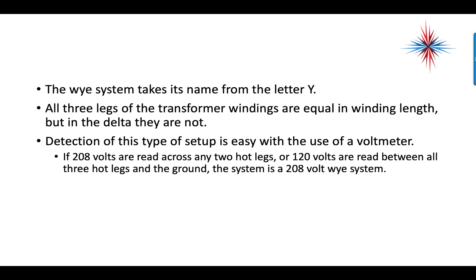The Y system takes its name from the letter Y. All three legs of the transformer windings are equal in length, unlike the delta where they are not. Detection is easy with a voltmeter: if 208 volts are read across any two hot legs, or 120 volts are read between all three hot legs and ground, the system is a 208-volt Y system.